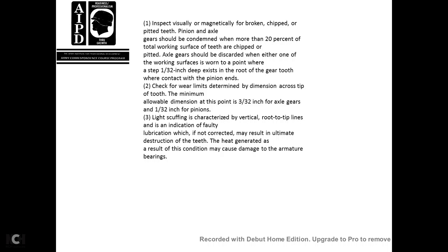3. Light scuffing of the teeth, characterized by vertical, root-to-tip lines, indicates faulty lubrication. If not corrected, it may result in ultimate destruction of the teeth, and heat generated as a result of the condition may cause damage to the armature bearings.